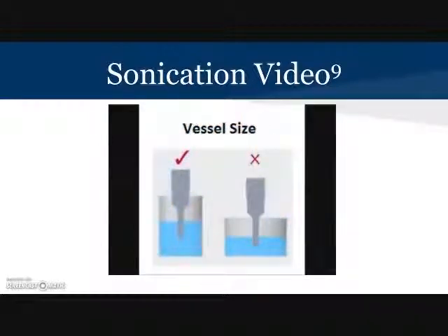A narrow vessel is preferable to a wide vessel. The ultrasonic energy is generated from the tip and is directed downward. As a sample is processed, the liquid is pushed down and away in all directions. If the vessel is too wide, it will not mix effectively, and some samples will remain untreated.